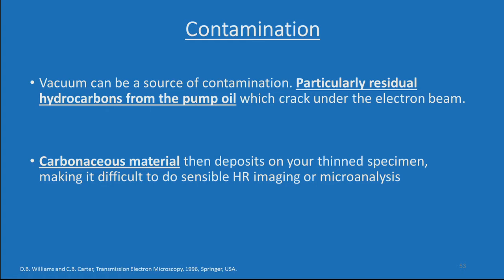We will now talk about a very important aspect of specimen-electron beam interaction: contamination. Vacuum can be a source of contamination, particularly residual hydrocarbon from the pump oil which cracks under the electron beam. Carbon then deposits on your thin specimen, making it difficult to do sensible high-resolution imaging or microanalysis. Any material coated on your sample — whatever you see as a new feature — may not belong to your specimen at all. So we have to be careful about this.